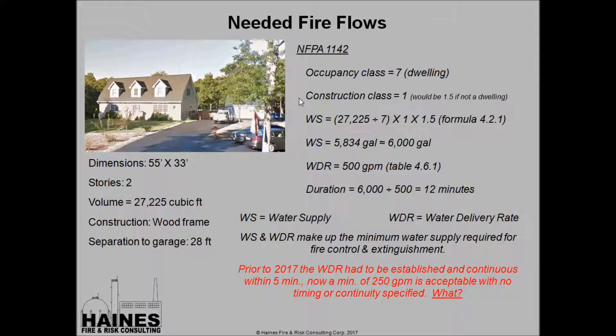NFPA 1142 is a little more difficult to use because you need a copy of the document. You're going to need to look up the occupancy class, which is a 7 for a dwelling, and the construction class, which is a 1 for wood frame construction. Interestingly, if the building were an office building, you'd be using a construction factor of 1.5.